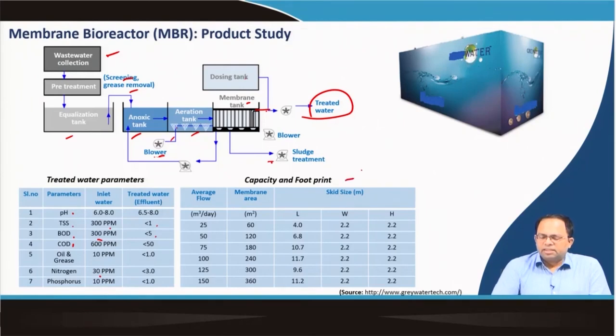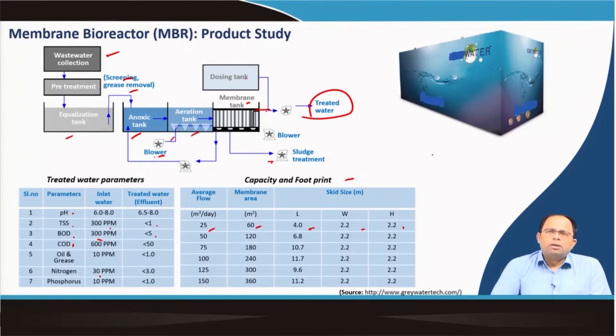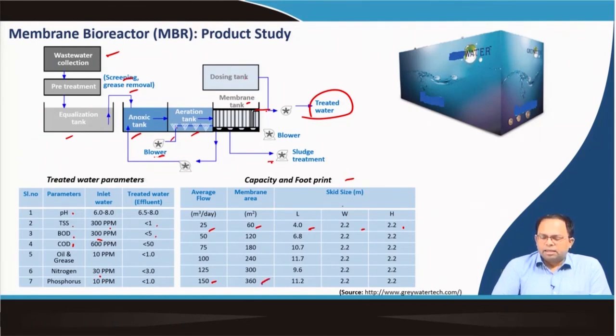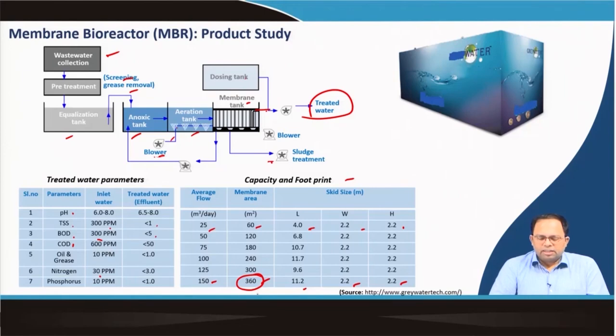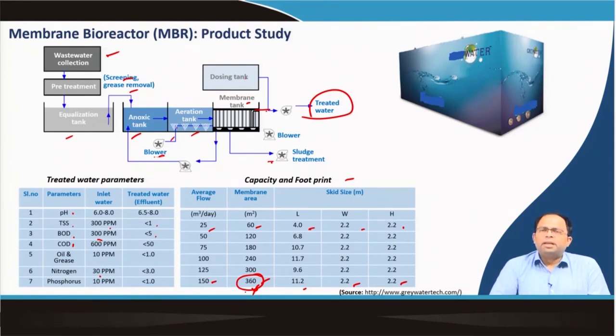For a commercial MBR product, to treat 25 cubic meters per day the membrane area required is 60 square meters, with dimensions of approximately 4 m × 2 m × 2 m. For 150 cubic meters per day, the membrane area is 360 square meters and the unit size is about 11.2 m × 2.2 m × 2.2 m. Since the membrane area is large, membranes must be organized — wound into spirals or arranged as stacked plates — to increase the surface area of contact. Membranes must be replaced at certain intervals and cleaned regularly, which are the main operational considerations of MBR systems, though they remain very compact and effective.